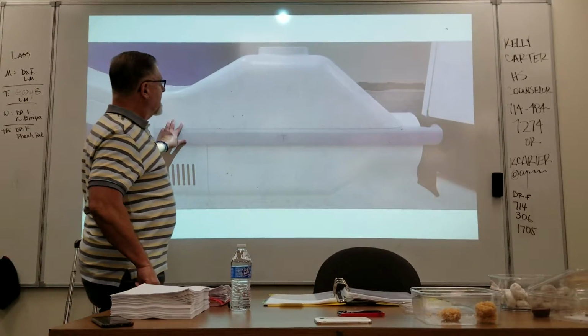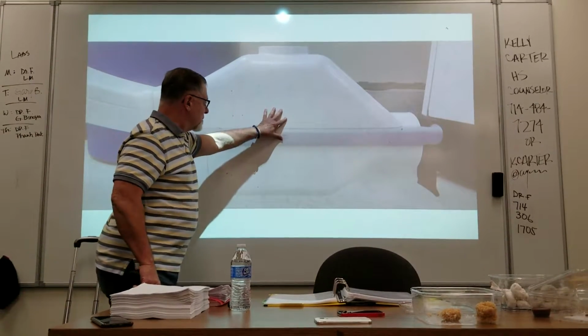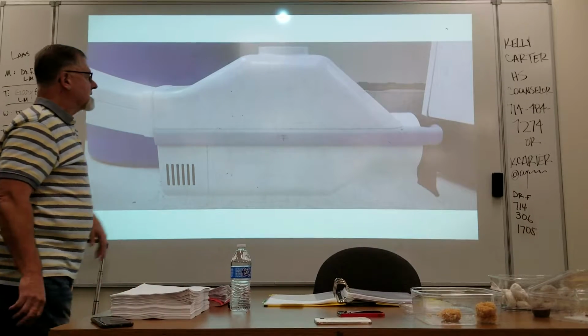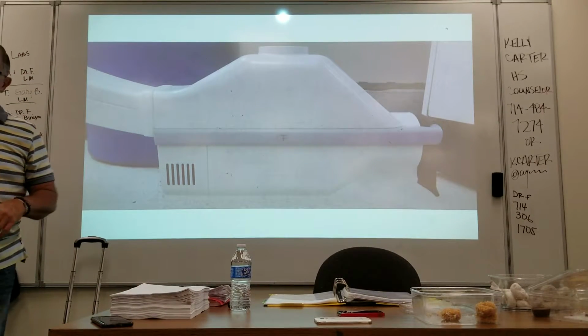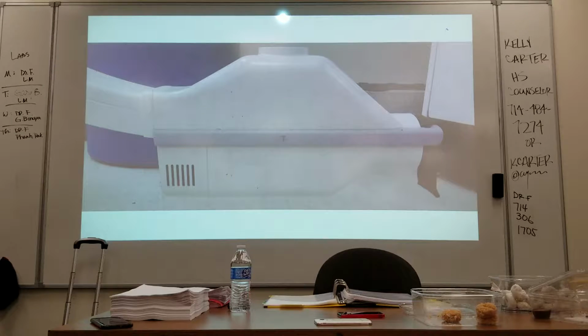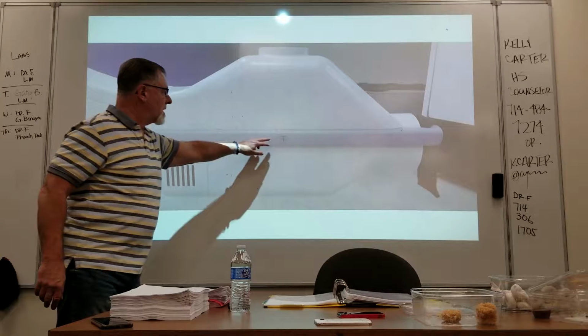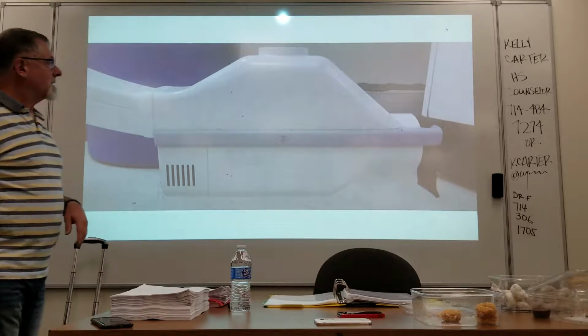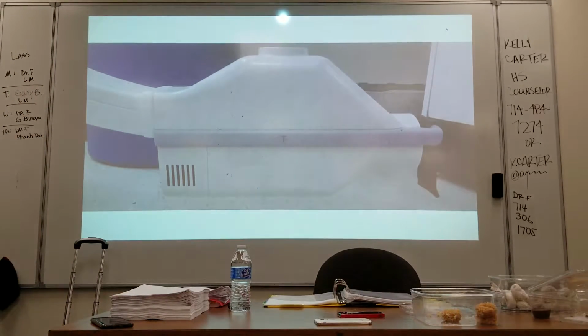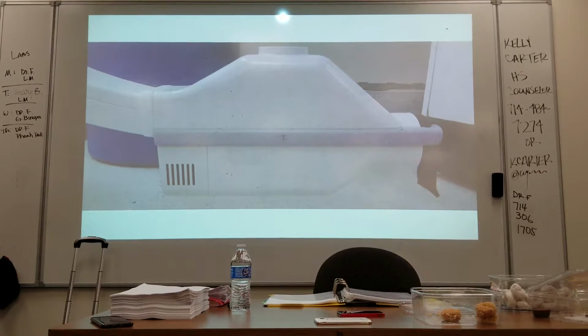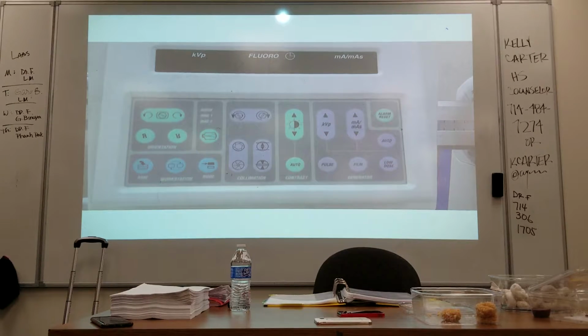But everything is in. A lot of these newer ones have not only the tube, but a lot of times in some of the newer units, part of the generator is actually in there. The high voltage system is in there as well. Generally, you can see where the focal spot is. And of course, that's to make sure that you meet the requirement for distance from the focal spot to the entry of the tube. We'll talk about that. This is another example where the controls are a little bit better explained.